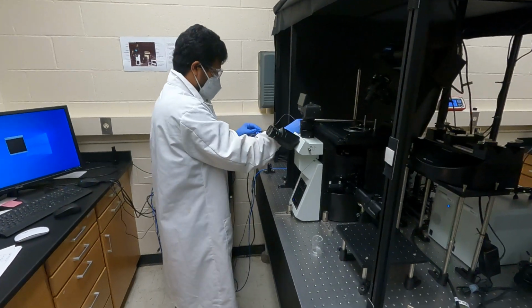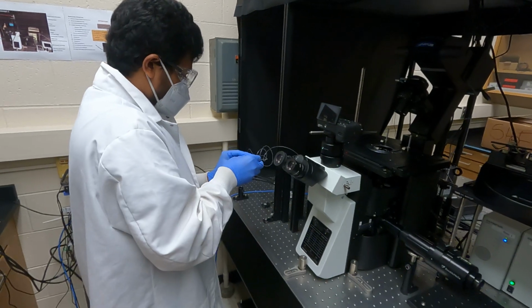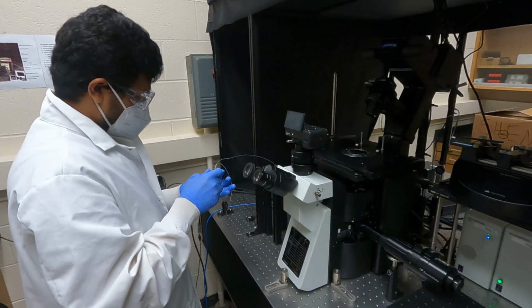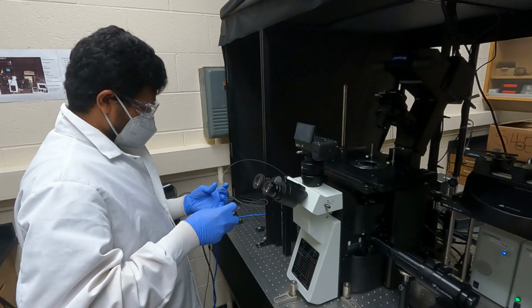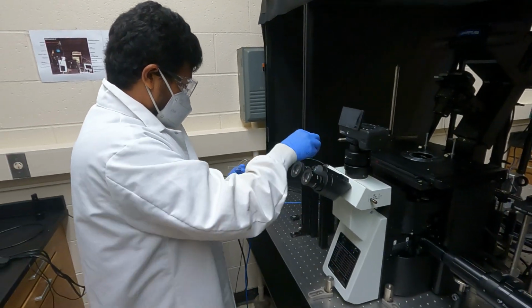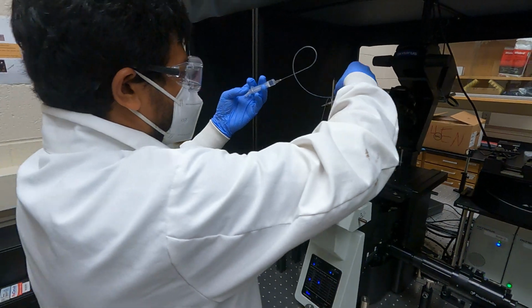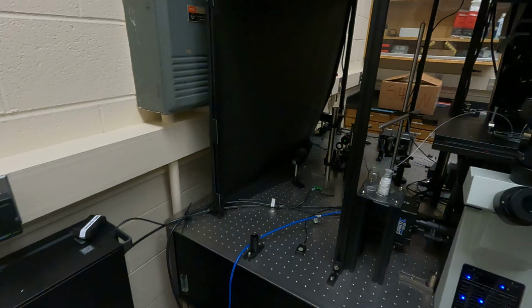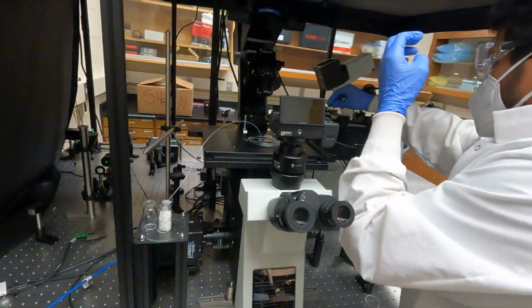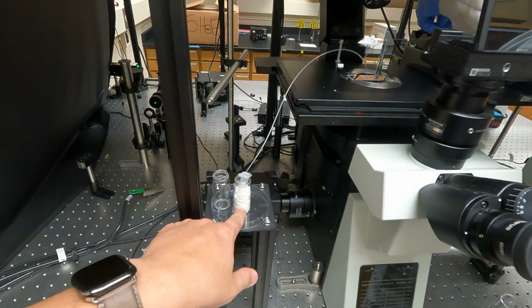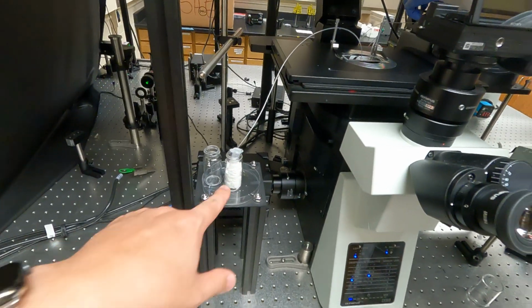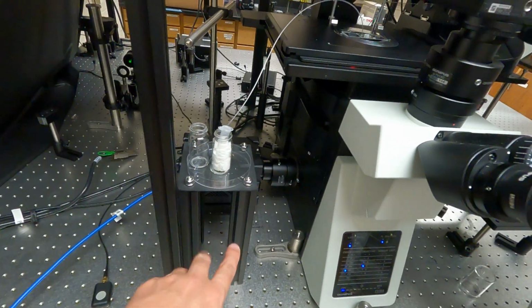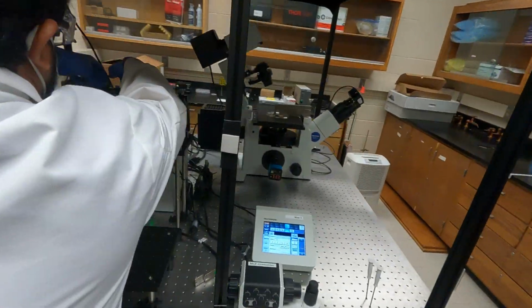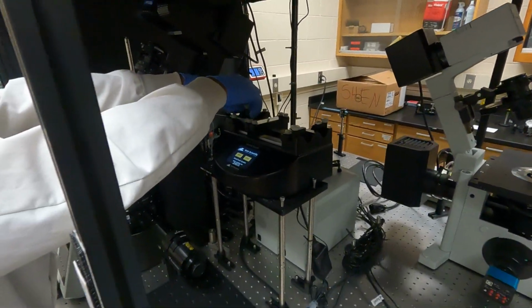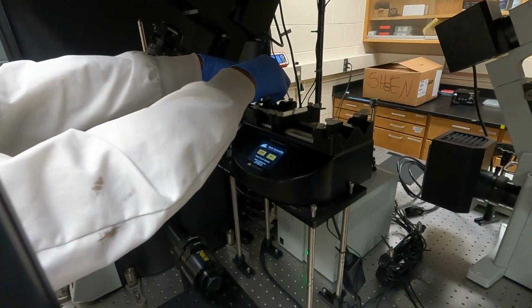Okay, now the actor is going to mount a completely assembled micro flow cell onto the microscope body. Typically, those flow cells will contain a reservoir where we store all of this reactant solution, and then usually they will place this reservoir here on this little stage. The other side of the entire cell connects to a syringe, and that syringe goes to a syringe pump.